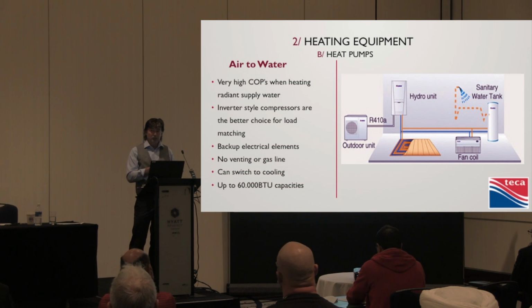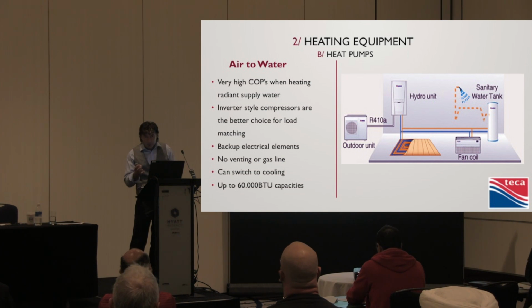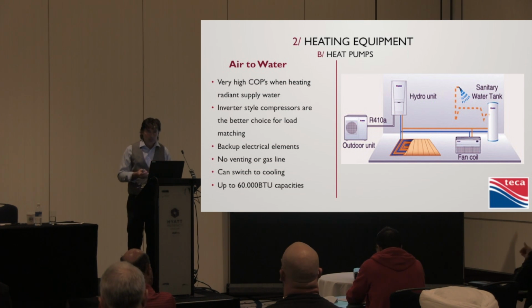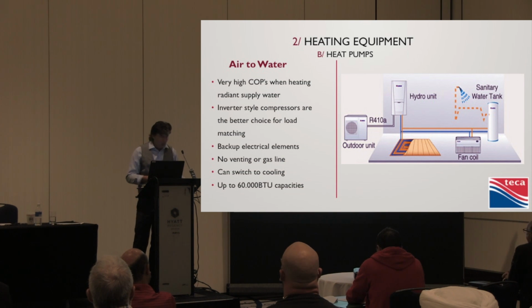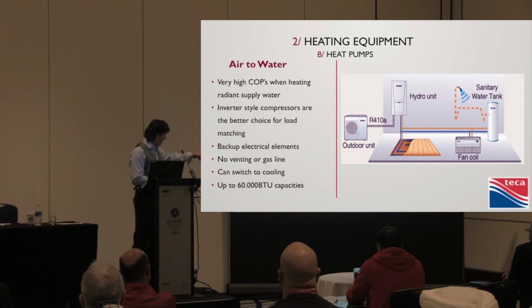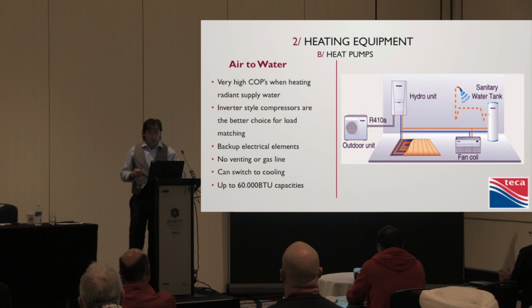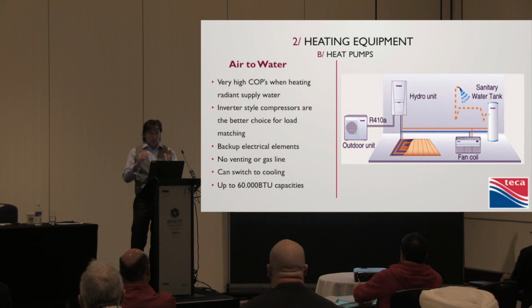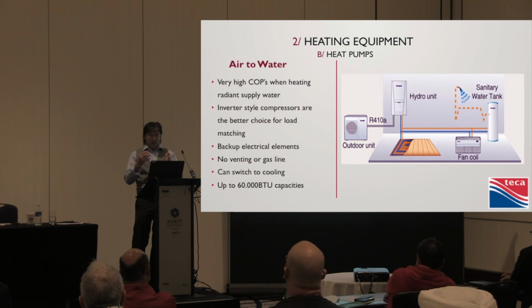You're coming on with 5 tons of capacity all at once. And that's all that thing knows. There are some North American models that are 2-stage, so a smaller compressor and a larger compressor, but nonetheless they're, shall we say, single speed. Inverter style compressors, which this thing utilizes, which is why I like this version, take single phase, convert it to 3-phase, and they modulate the electricity that goes into the compressor.